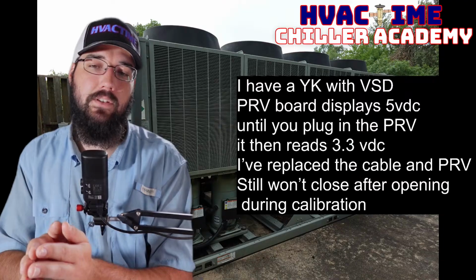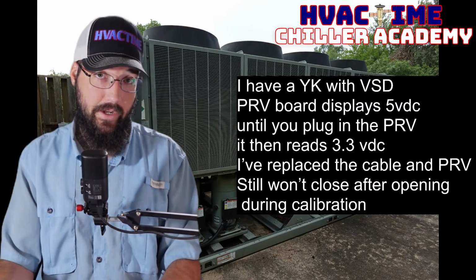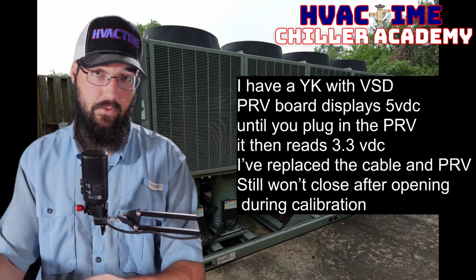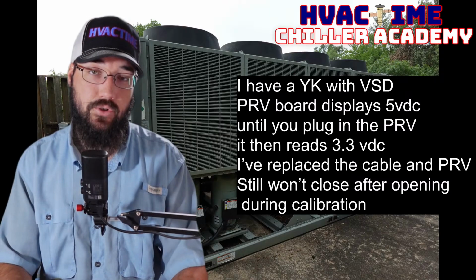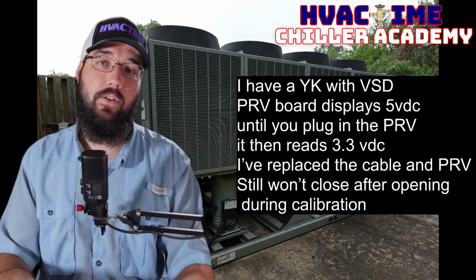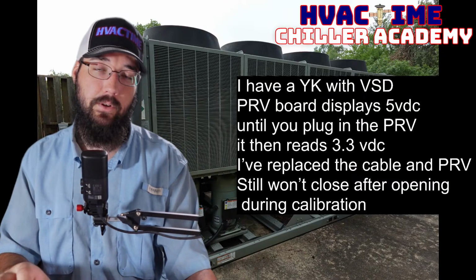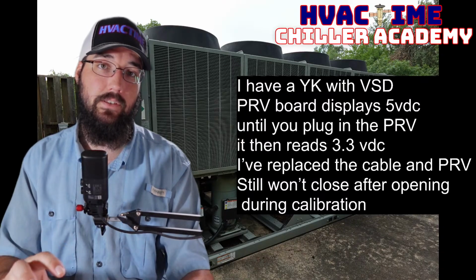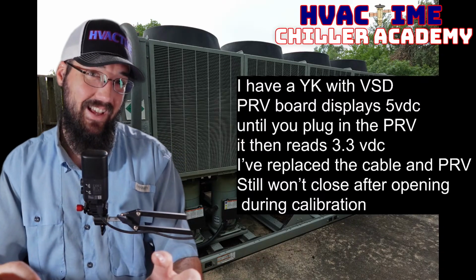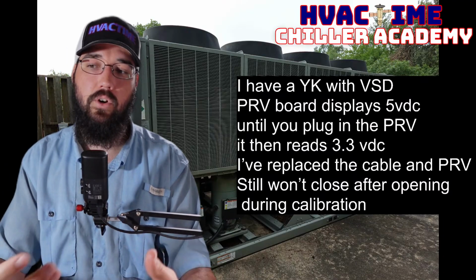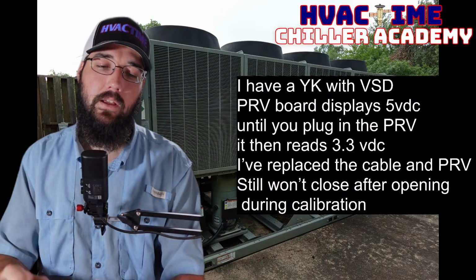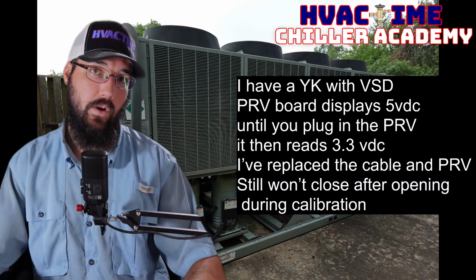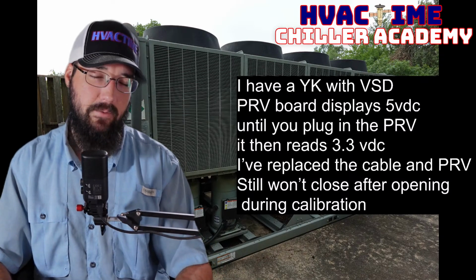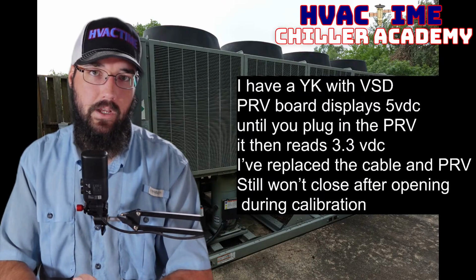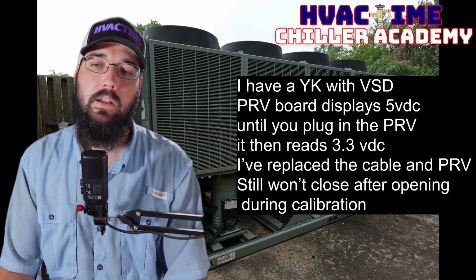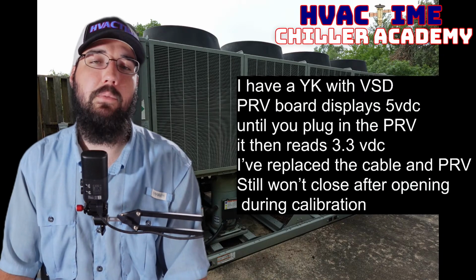Now, if it's not the module, then it could be just an improper wiring. Those actuators are pretty intricate in what wires need to land where, and they do change from model to model. I've found that when I was replacing an older style actuator motor with a newer one on those YKs, the schematic wasn't like for like. They were slightly different, and I had to do some work and thinking to make sure I got everything landed where it needed to be. So that is something that could have happened. Maybe there's a wire out of place, maybe it didn't get wired back just right, or that module seeing that drop could definitely be a problem. Yeah, that would be the two directions I'd want to go.